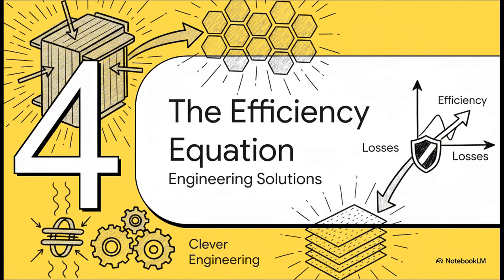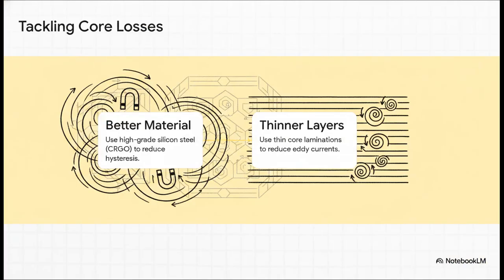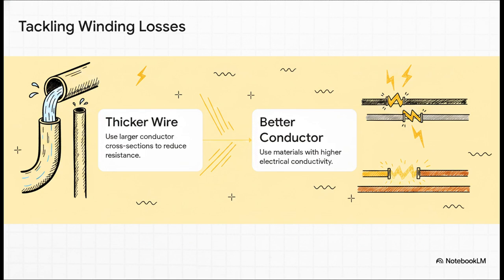So, now that we've identified the culprits, the big question is, how do we fight back? This is where some really clever engineering and materials science come into play to try and minimize these inevitable energy losses. So, to cut down on that hysteresis loss, engineers use a really special material called CRGO silicon steel. Its grain structure is designed to make it much easier for those tiny internal magnets to flip back and forth. And to stop those pesky eddy currents? Well, the core isn't one solid block of metal. It's actually built from hundreds of ultra-thin steel sheets, each one insulated from the next, which breaks up the path for those electrical whirlpools.